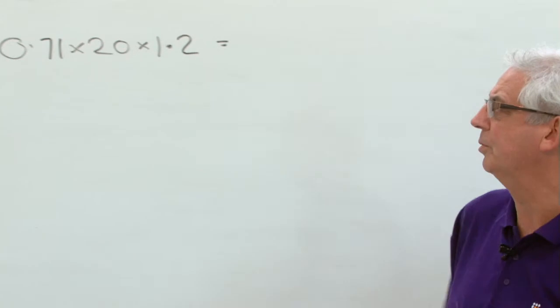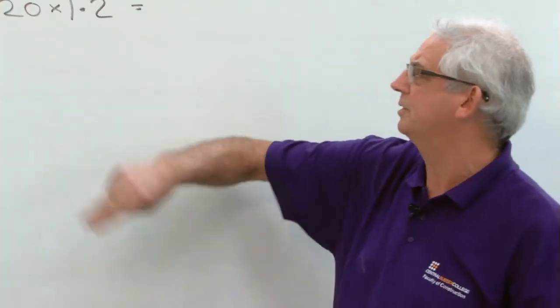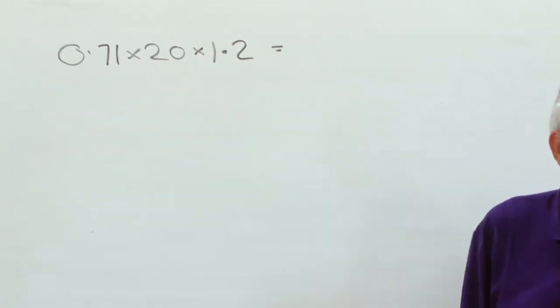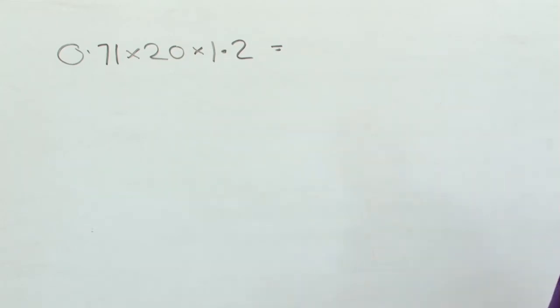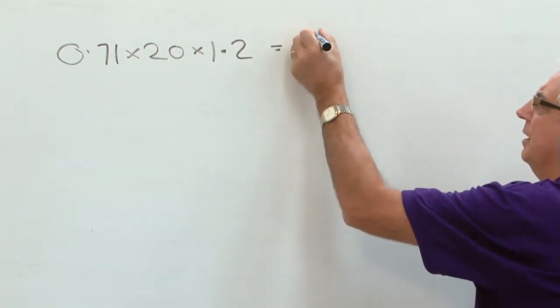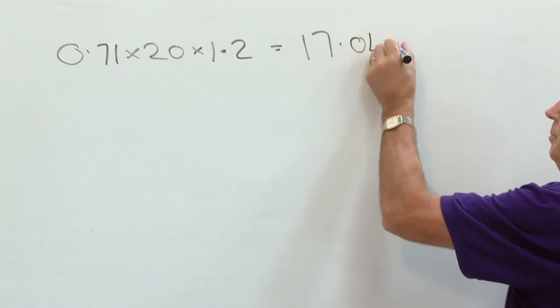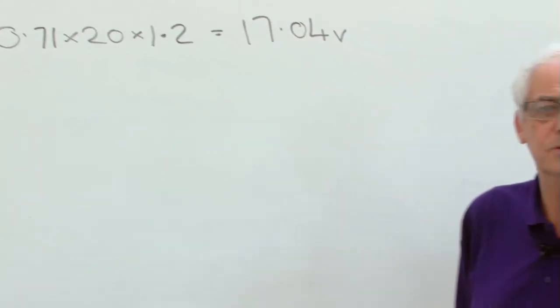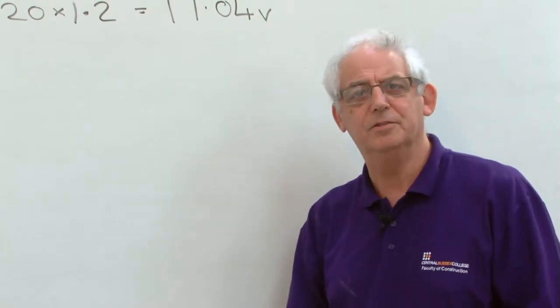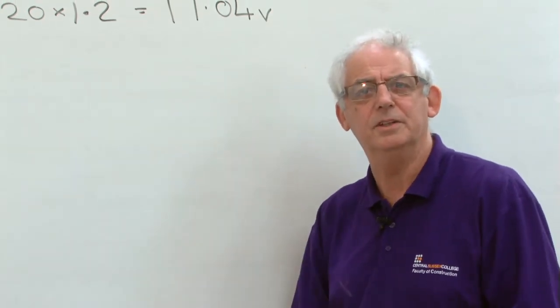Now if I multiply all three together, I've got the resistance times the current which is really just Ohm's law, multiply it by 1.2, I'm going to end up with a value of 17.04 volts. Now clearly that's far greater than the 5% I would be allowed for this circuit, 5% of 230 is 11.5 volts.